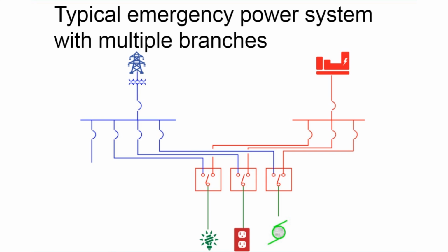A patient care area is required to be served by devices connected to both the normal and critical branch. To understand this requirement, you have to look at the single point failure on our distribution system. So we talked about making sure that no one feeder can allow any area within the building to lose power entirely. The same single point failure approach is applicable to many types of high performance occupancies.